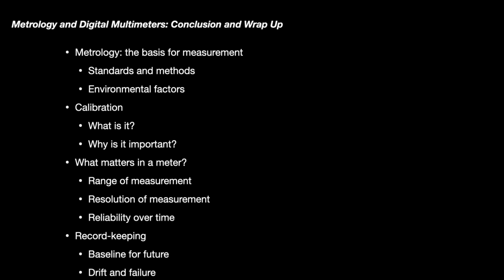We learned about calibration. We learned what it wasn't, which is taking a screwdriver and adjusting things every time the meter doesn't read 10 volts when you think it ought to. Rather, keep a record of what the measurement was on a recognized, stable, reliable voltage. And if it changes over time, like a year or 2 years, maybe the meter needs to be recalibrated professionally. We talked about what matters in measurement, and I think there's enough said about that. Record keeping will always be an important part of this because the task of an engineer and the task of a technician out in the field remains the same: reporting back on what should be done, what was done, and what remains to be done.